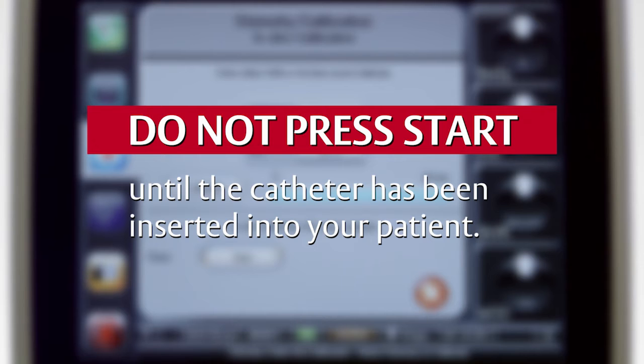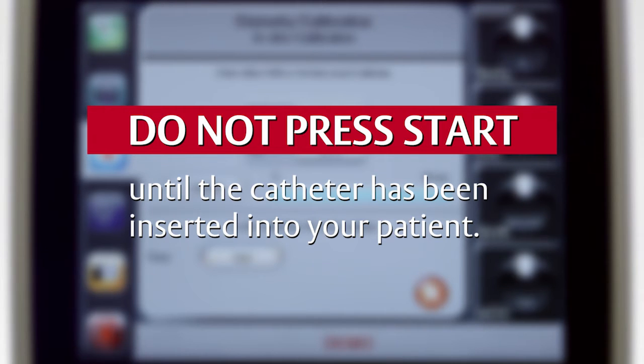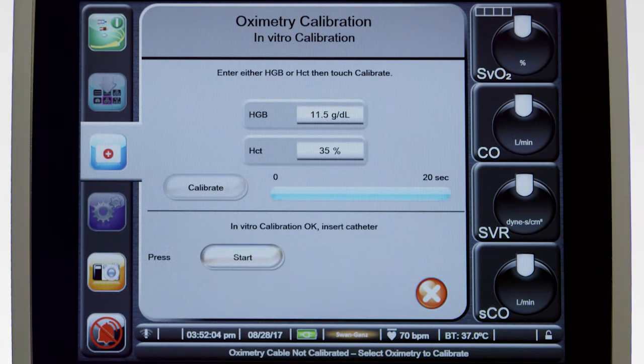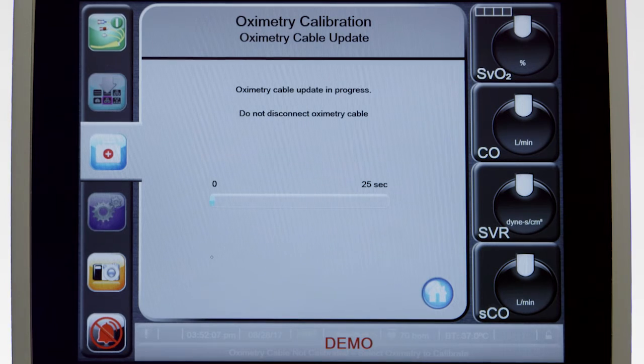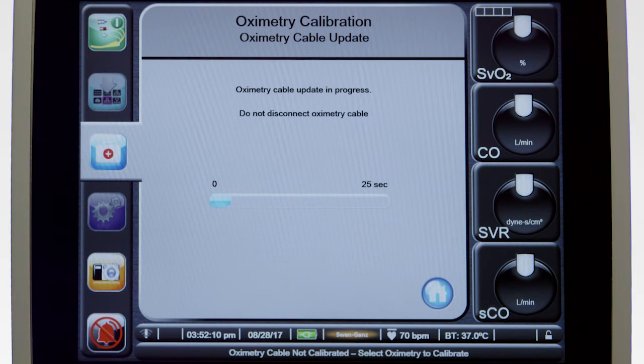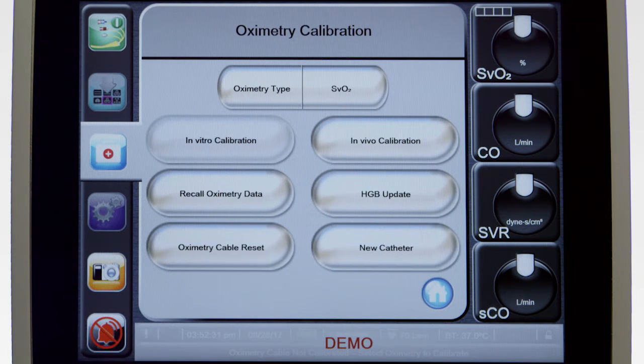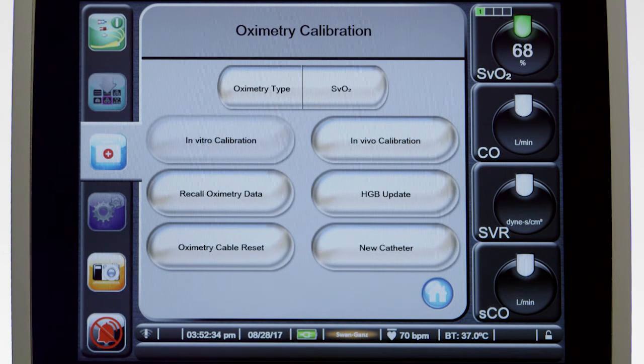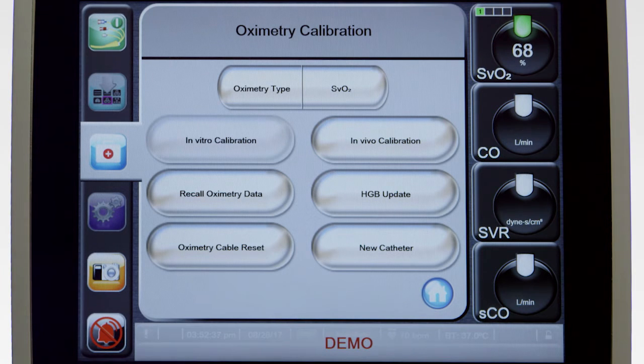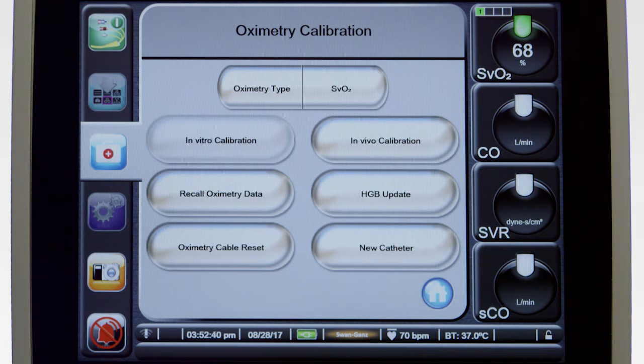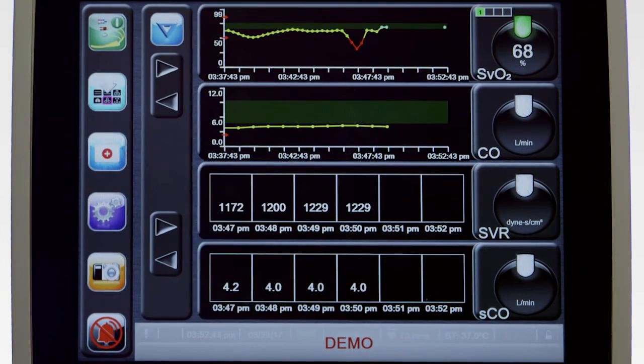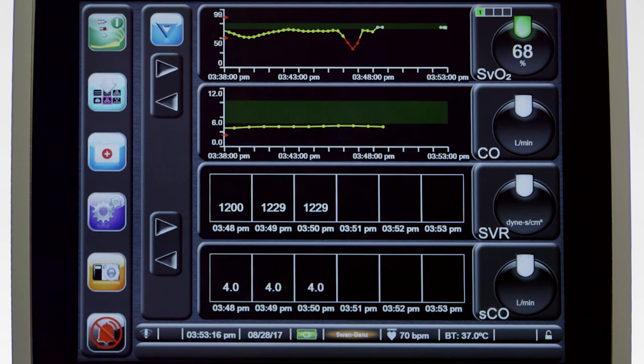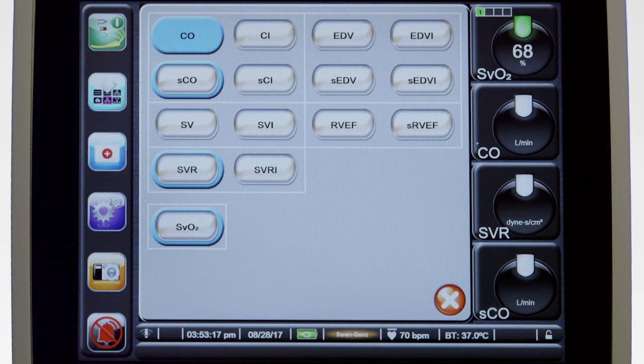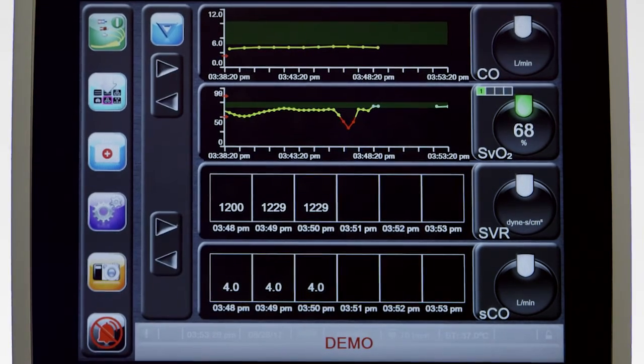Press Start. The Start button will appear. However, do not press Start until the catheter has been inserted into your patient. To begin recording oximetry values, insert the catheter into your patient and touch Start. Oximetry recording will begin. After 25 seconds, the SVO2 reading will be displayed and will update every 2 seconds. Once completed, the in vitro calibration cannot be repeated and the in vitro calibration button will be disabled. Press the Home icon. If the SVO2 parameter is not displayed on the screen, touch the gray square surrounding one of the parameter globes and select SVO2 from the parameter list.